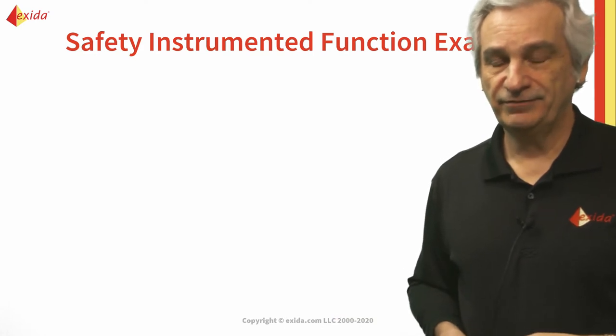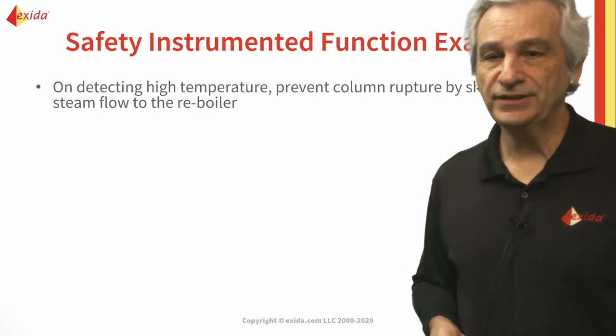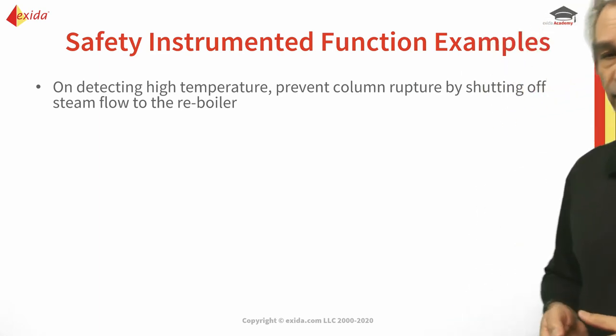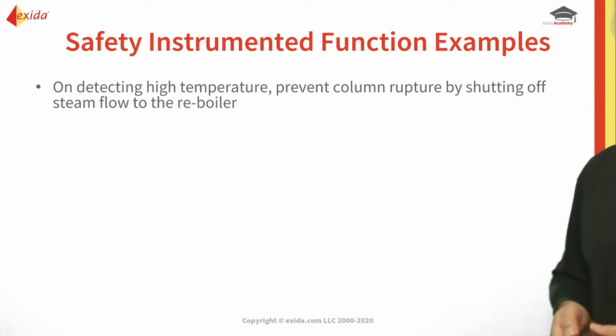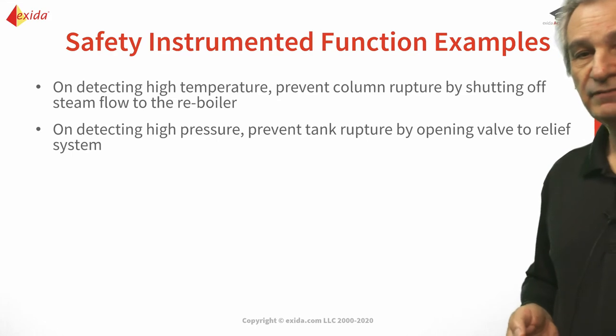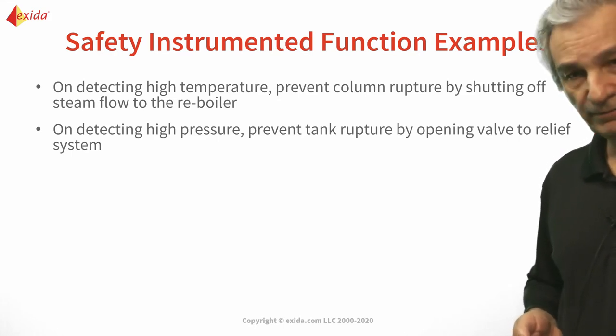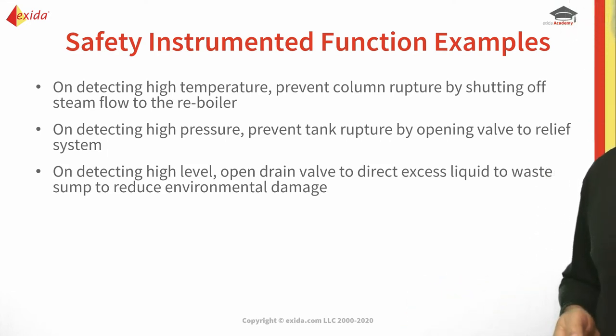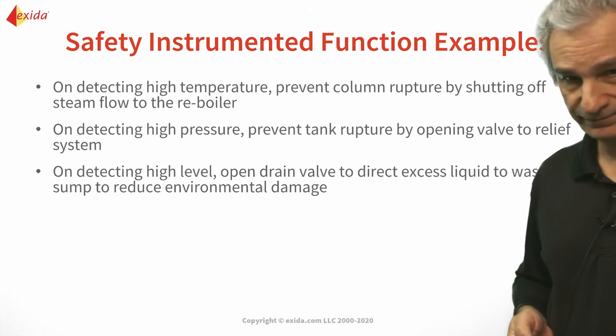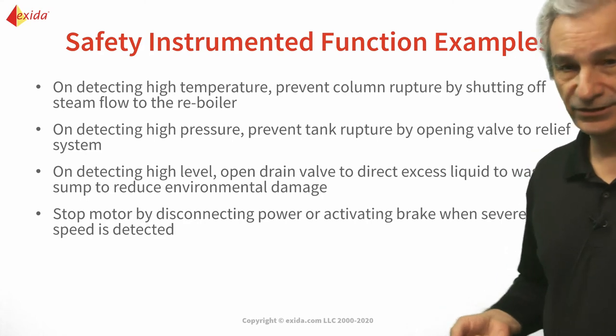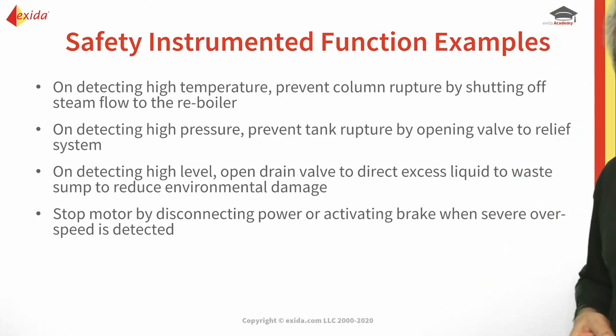Examples of safety instrumented functions: On detecting high temperature, we want to prevent column rupture by shutting off the steam flow to the reboiler. On detecting high pressure, we want to prevent tank rupture by opening the valve to the relief system. On detecting high level, we open the drain valve to direct excess liquid to a waste sump to reduce environmental damage — so that's a level protection function.